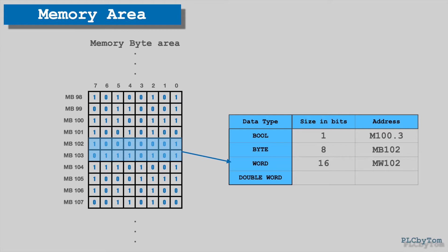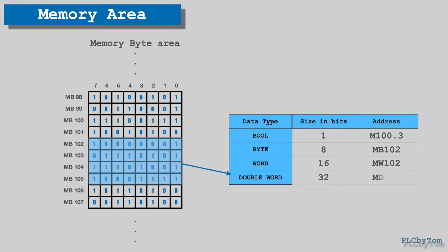So by this it is accessed to the byte 102 and 103. In the same way it can be addressed as double word or four bytes long data by format MD102, where letter D represents double word. In this case it is addressed to data four bytes long starting from byte 102.